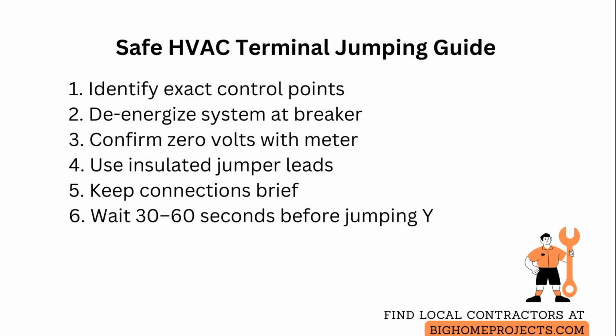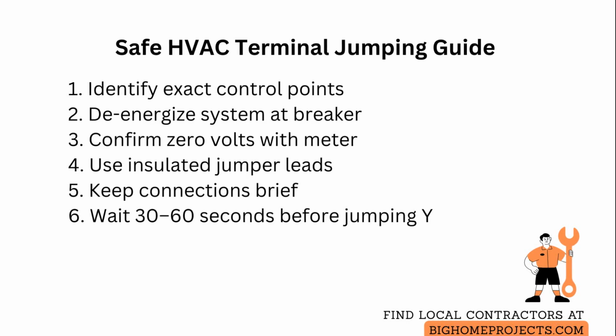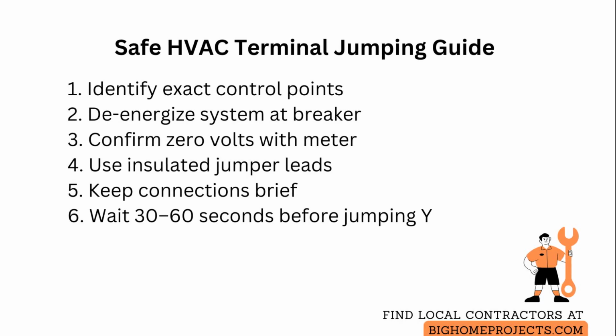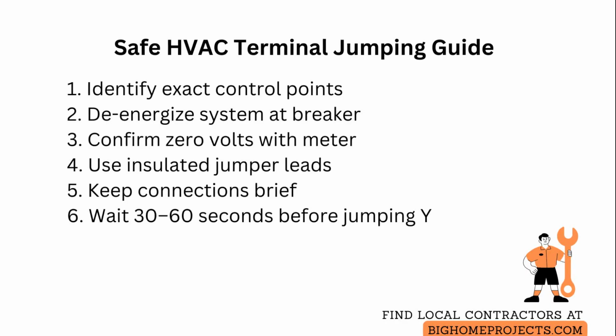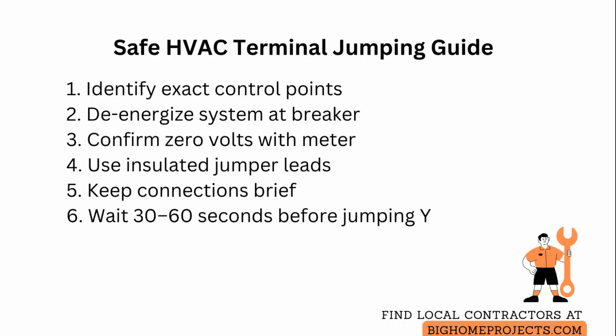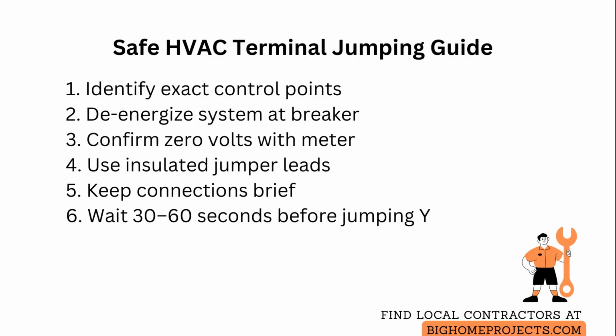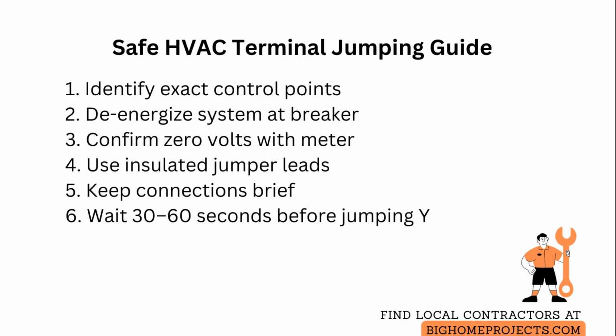When you need to inject a signal, use a properly rated jumper lead and, when possible, use a multimeter to verify the actual voltage and continuity before connecting. If the system has electronic controls or a building automation interface, prefer simulated inputs or software overrides rather than hardwired jumpers because modern boards can latch faults or store error states that require a power cycle or factory reset to clear.